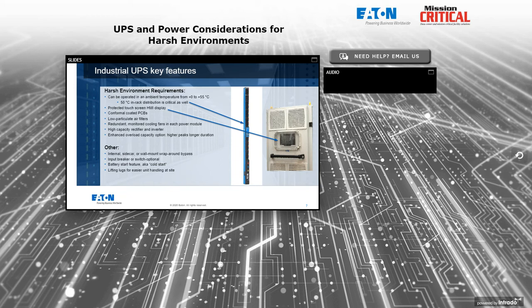Other things like an internal, sidecar mounted, or wall mounted wraparound bypass. Just as important in any UPS application is a wraparound bypass, also known as a maintenance bypass. It should ideally be separate and isolated from the energized circuitry inside the UPS so that I can de-energize the entire UPS for service without interrupting power to my critical devices and without having any live componentry inside the UPS, so I can service it safely.